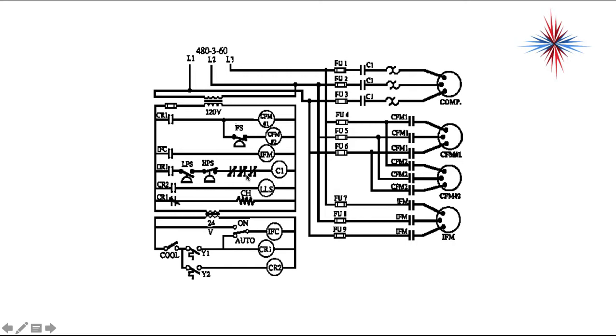Here, these are normally closed. If I took an ohm reading from here to there, I would have a path for electricity to flow through that load. However, there's a pressure switch here that's normally open, and there's a contact here that's normally open. So there's no current coming through this leg of electricity. So again, when you see a big schematic, break it down into individual pieces. We're going to read it from top to bottom, left to right, just like you would a book.